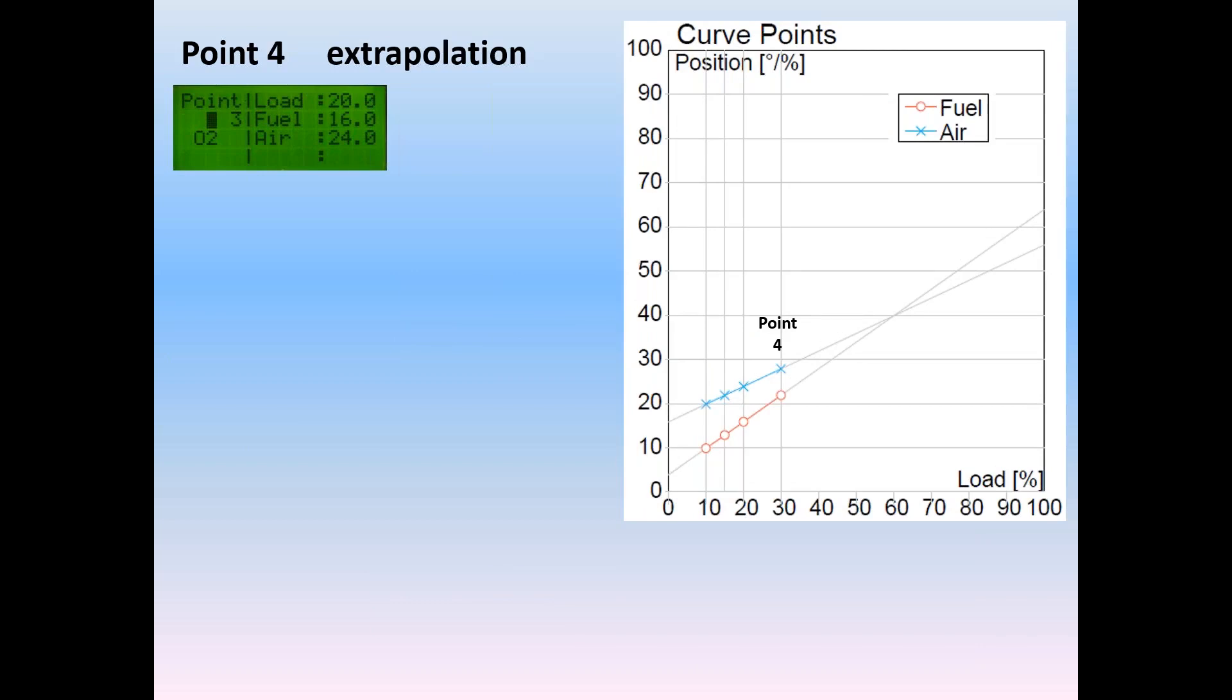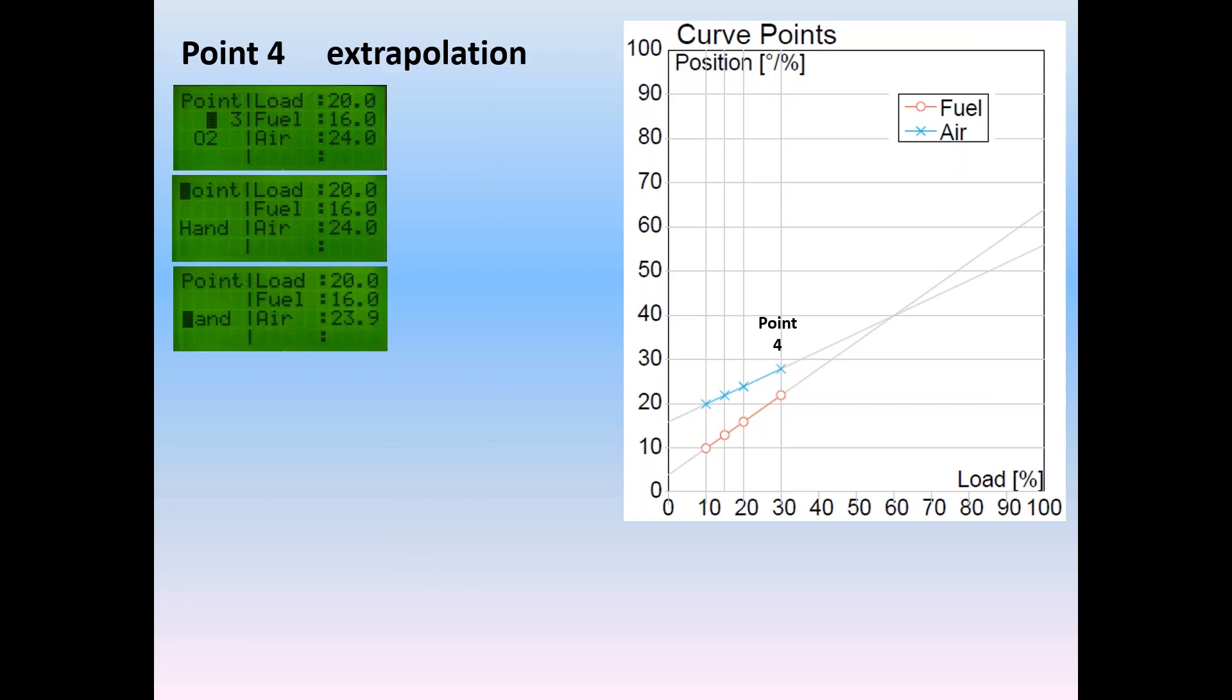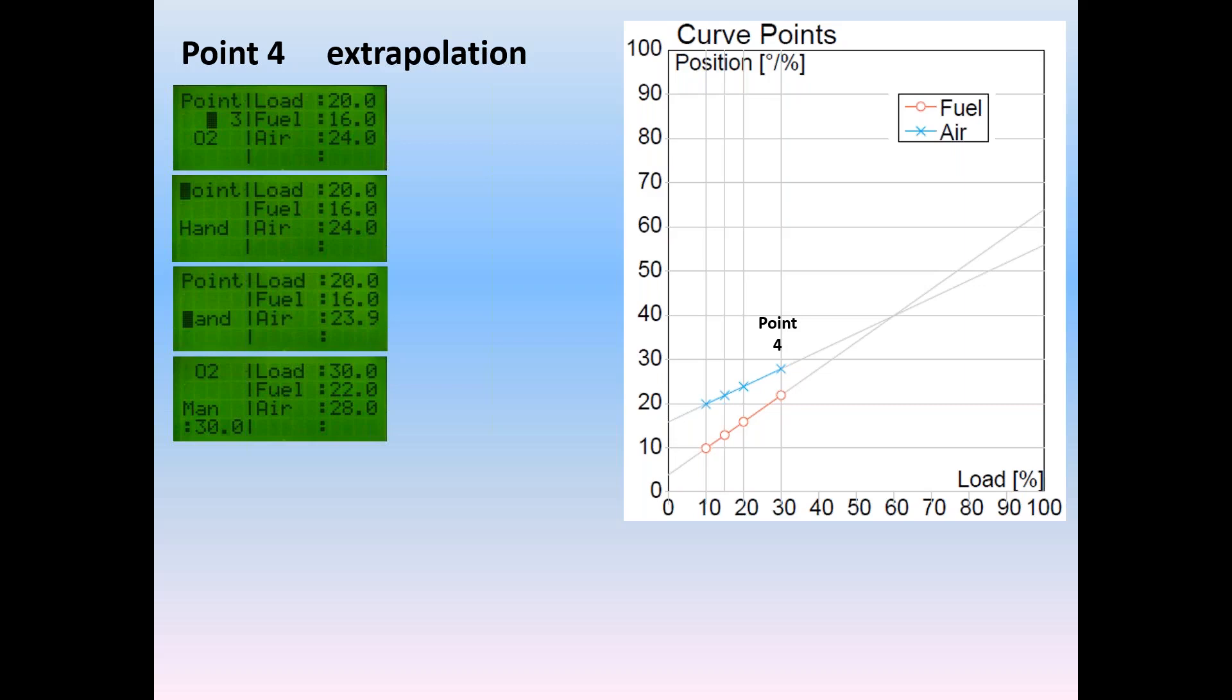This time instead of entering point rather go down to hand and enter the hand portion of the menu. When you do it'll say manual and then a load number will come up. I have points in there for 10 percent and 20 percent. So if I adjusted my load to 15 percent you're going to see it's going to be exactly halfway between point number one and point number two. Once I'm on there I can enter and now I'm on point number three which is 15 percent load and the values would be halfway between what they were between point one and point two and I can make adjustments on that and store the point. Once I store the point that goes in there and see it says point number three is 20 percent load but as soon as it enters into the table you notice that it renumbered them. Point number one is 10 percent, point number two is 15 and point number three becomes 20 percent. Points are always in load number order. Don't fall in love with your point number. Fall in love with your load number.